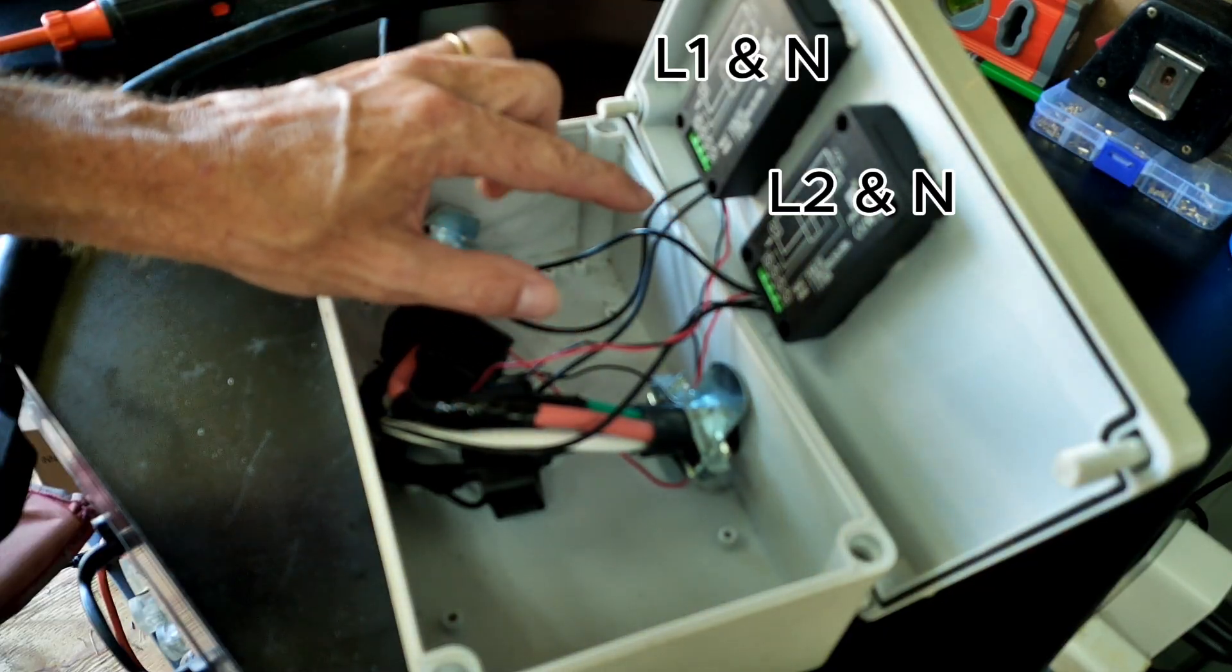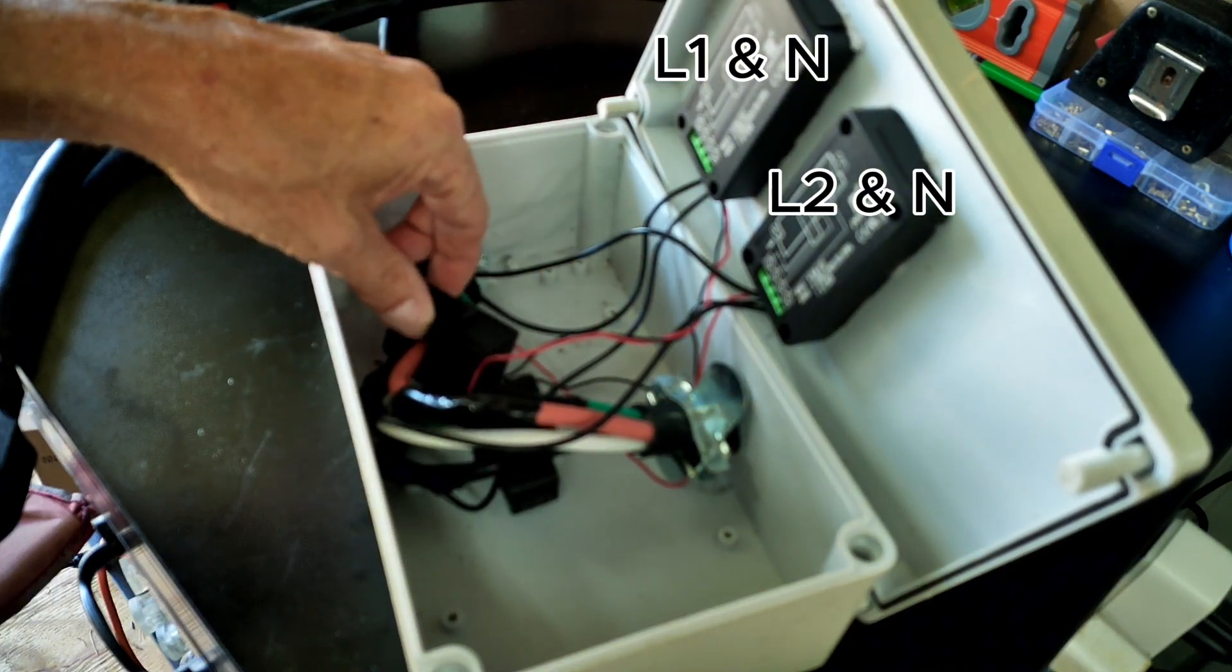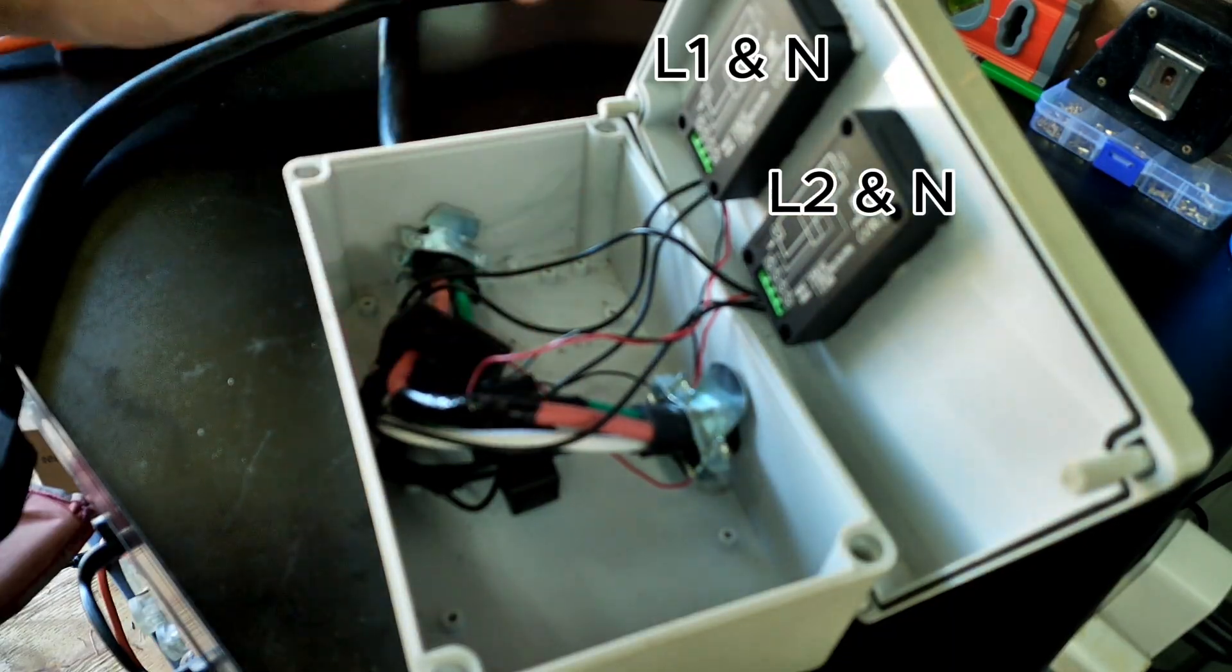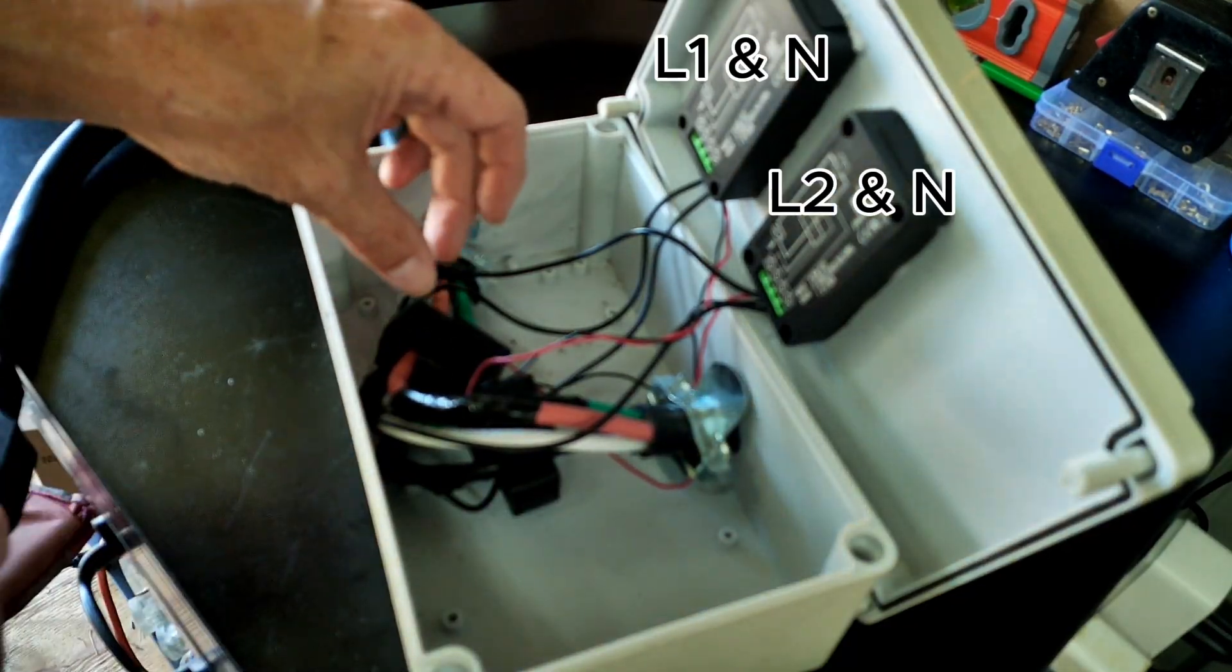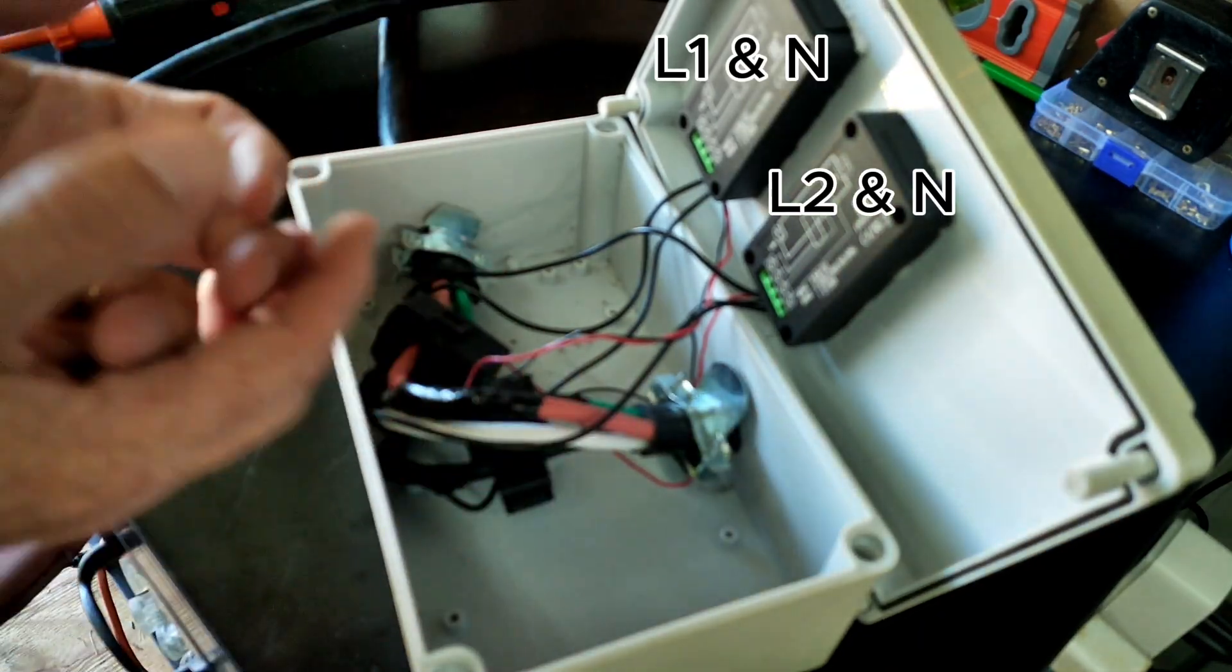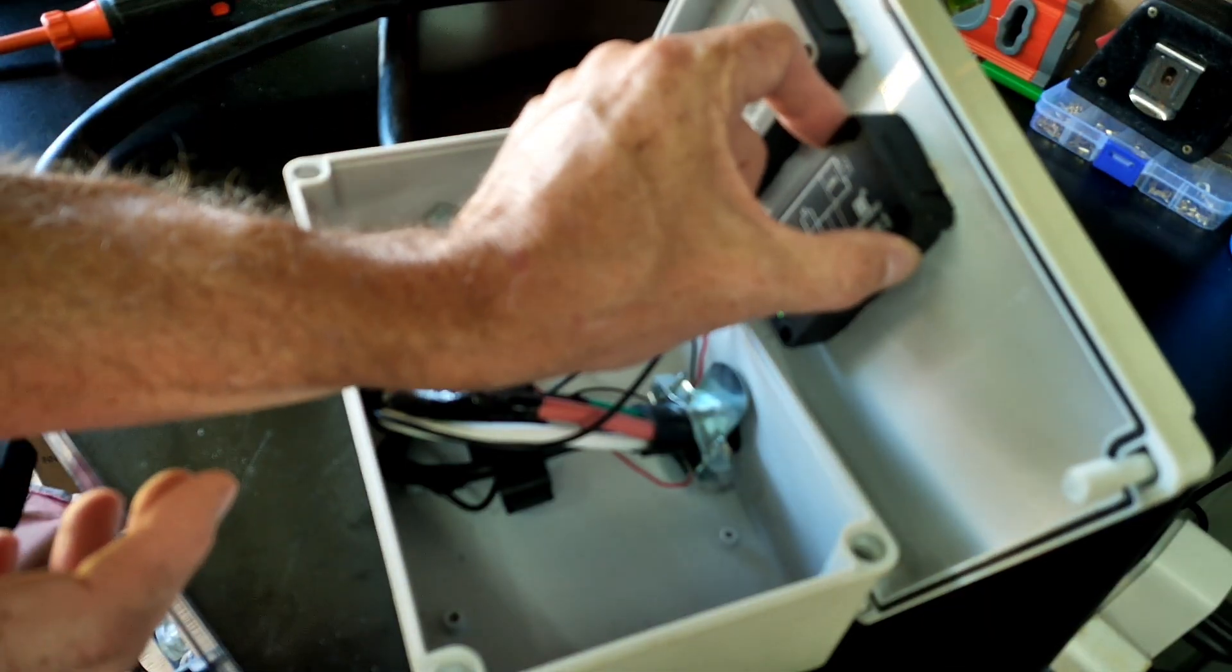Now the smaller wires run to the CT clamp. As you can see, the CT clamps, one runs around L1 and one runs around L2. It's a very simple device. Technically you could take one of these CT clamps and wrap it around both the red and the black wire and have one CT clamp measure both sides. That would cut the cost of your meters in half because you would only need to buy one instead of the two pack that's included in the parts list below.